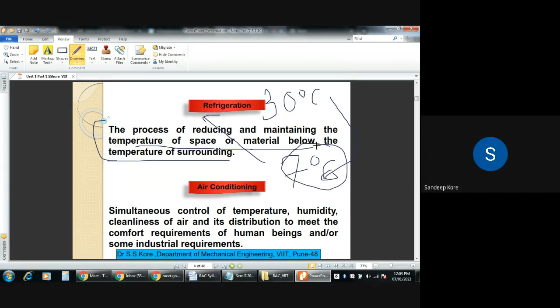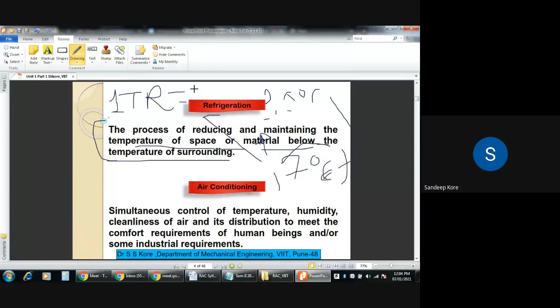So this refrigeration effect is measured in terms of the unit of refrigerating system, which is 1 TR. 1 TR means 1 ton of refrigeration. It is defined as the amount of cooling effect produced by melting 1 ton of ice from and at 0 degrees centigrade within a period of 24 hours.